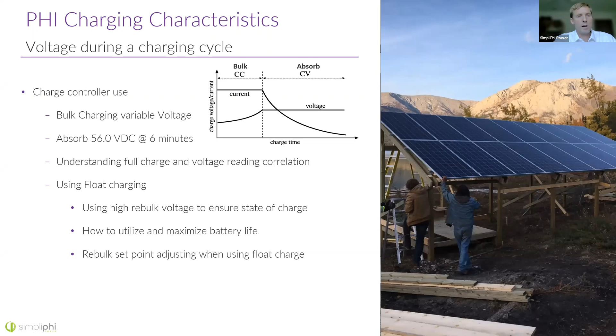Okay, so inverter capability: you want to make sure that your inverter has the ability to have all of these set points programmed into it. When you program your inverter for battery commissioning, you want to make sure that you have your voltage set points properly set so that the battery doesn't overcharge. The time when batteries get damaged is either when they are cycled way down to 0% state of charge, or they're cycled way too high to 100% state of charge and you've got a high voltage on the battery. Normally that's the time when your battery is most vulnerable. So you don't want to be overcharging these batteries and you don't want to over discharge them. And I'll get into discharging in the second half of this presentation.